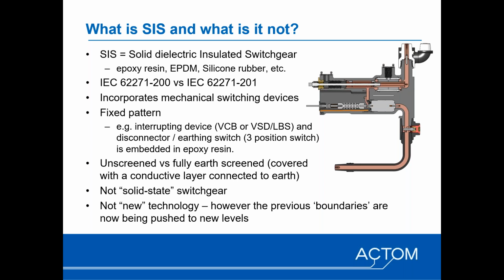So the other key aspect to consider and talk about when it comes to SIS switchgear is whether or not it is unscreened. In other words, it's just embedded in epoxy or solid dielectric insulating medium, or whether it has a fully earth-screened conductive layer on the outer surface. And we'll go into details about the impact of the two different designs. The other point to mention is that effectively it's not a new technology. This is not something that suddenly appeared.